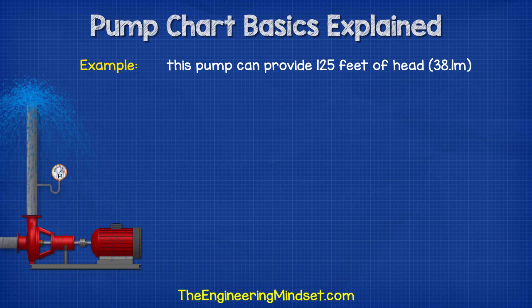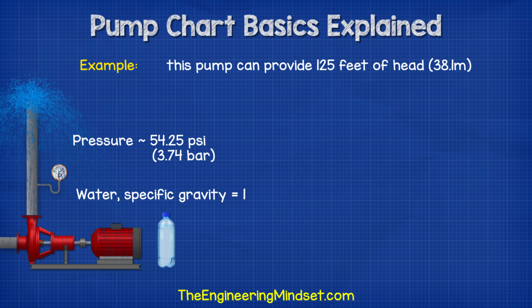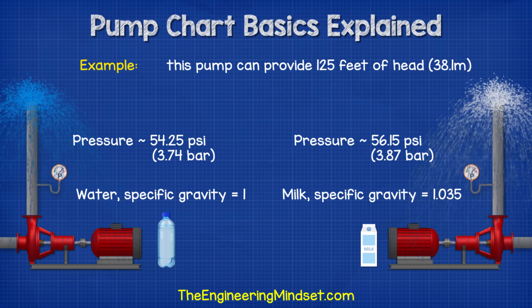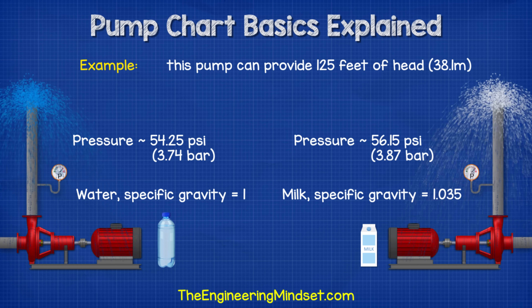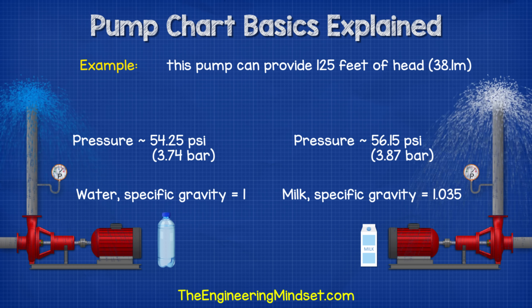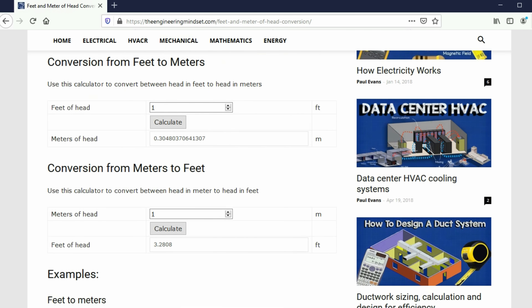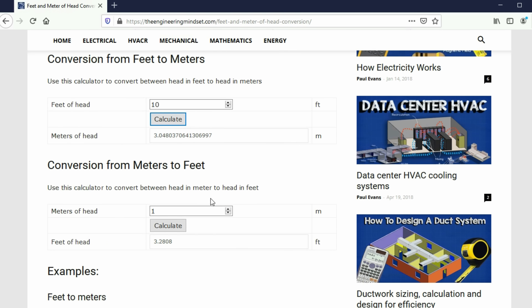For example, we have this pump which can provide 125 feet of head. If we use it to pump water, the pressure will be around 54.25 PSI. But if we were to use it to pump milk, then the pressure will be around 56.15 PSI — and that's purely because of the properties of the two fluids. Conversion between feet and meters of head is very easy; we have a free calculator for that, which you can find links to in the video description below.